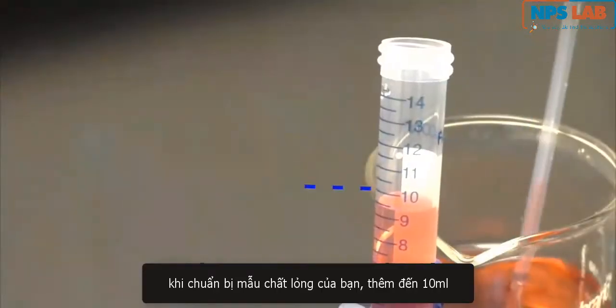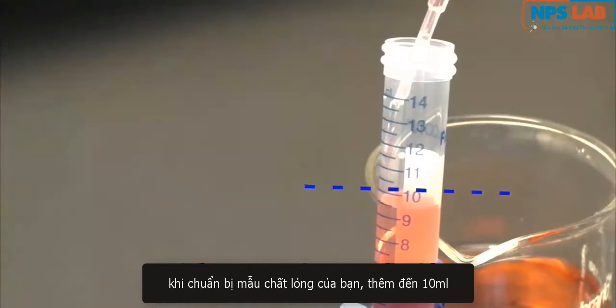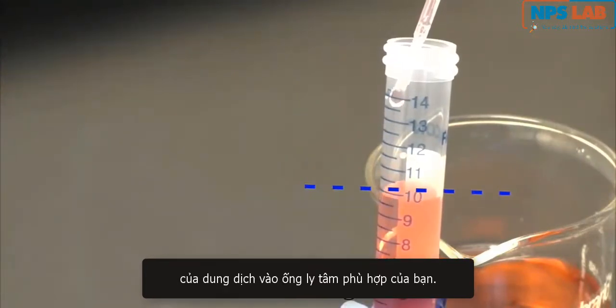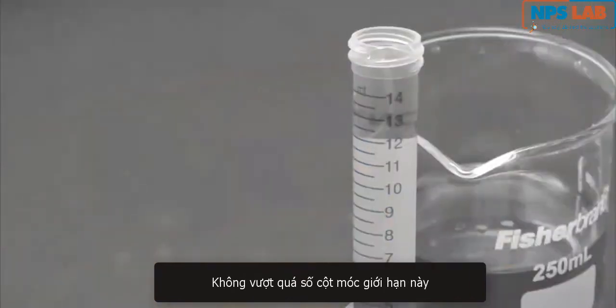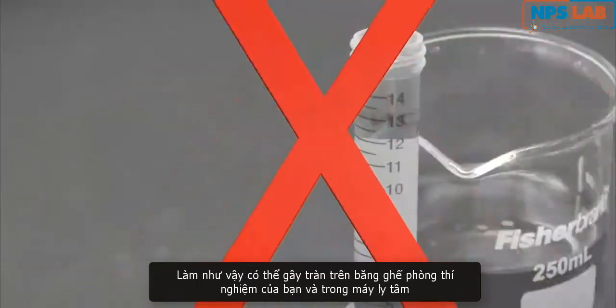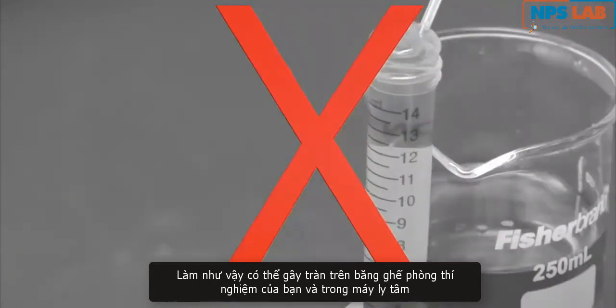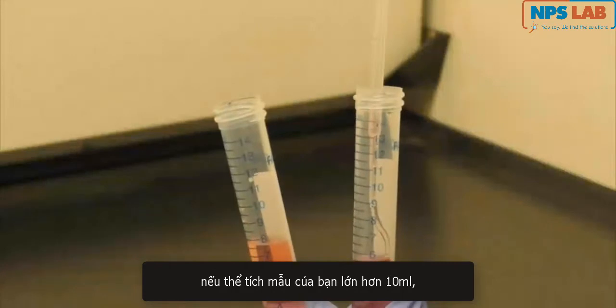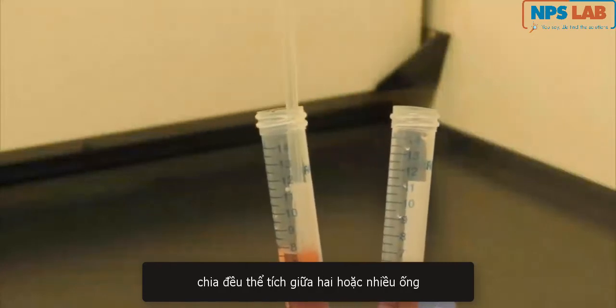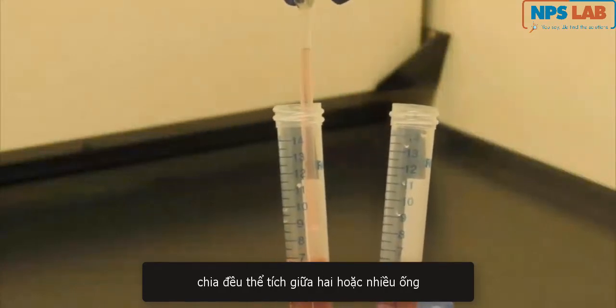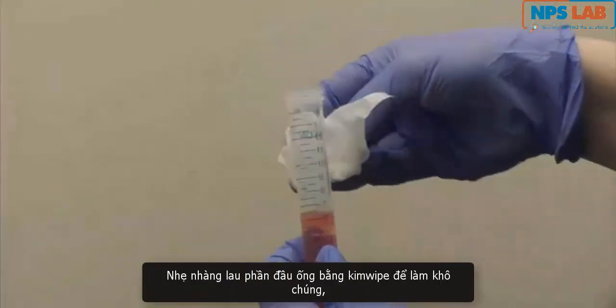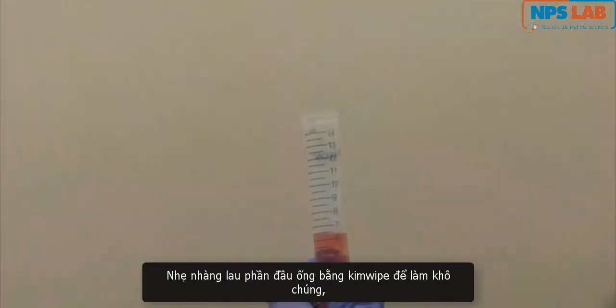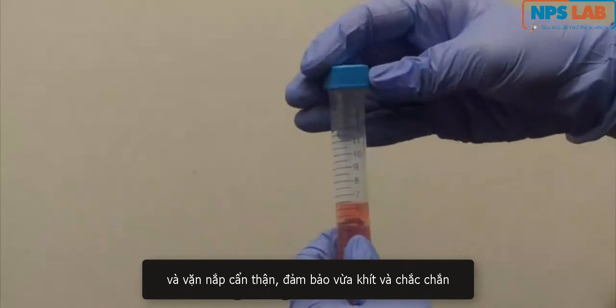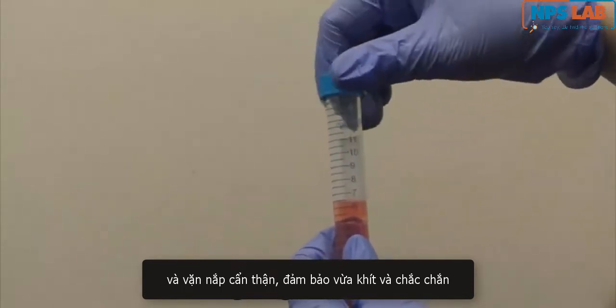When preparing your liquid sample, add up to 10 milliliters of solution to your suitable centrifuge tube. Do not exceed this amount. Doing so can cause spills on your lab bench and in the centrifuge. If your sample volume is greater than 10 milliliters, split the volume equally among 2 or more tubes. Gently wipe the threads of the tube with a Kim wipe to dry them and screw the cap on carefully, ensuring a tight and secure fit.